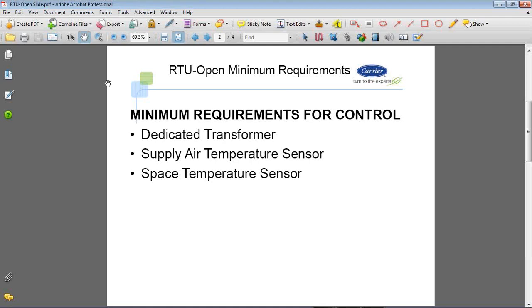Now, because these boards are Bacnet native and can be integrated into other control systems, you can use a supply temperature or space temperature sensor from the building automation system, meaning it doesn't have to be hardwired to the controller. You can take that point up via the network, but it somehow needs these values in order to function. It cannot go through its logic to control the rooftop without them. So that's bare bones. If you need that controller to function, you need those two sensors and a dedicated transformer. We also include with these rooftop controllers a wiring harness of how it wires into the thermostat terminal board, which I'll show you on the next slide. But that's kind of a side note. We always include those as standard.